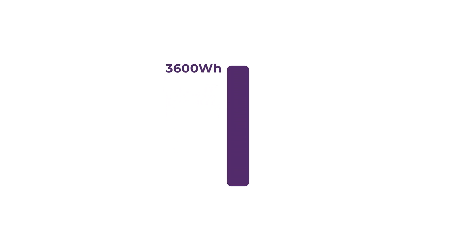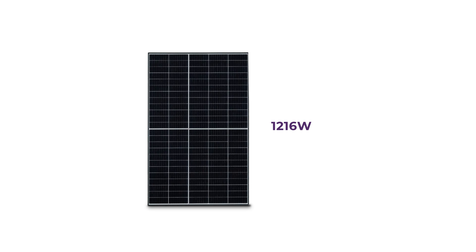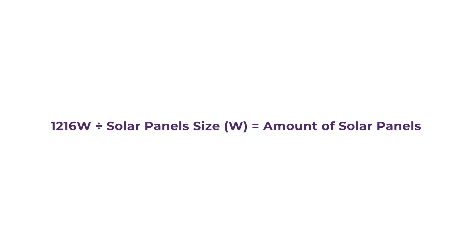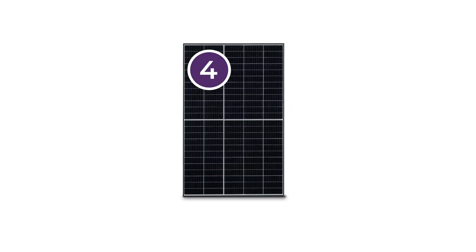For example, if you need to generate 3,600 watt hours a day to support your power use, you can then divide that by the peak sun hours. So 3,600 watt hours divided by 2.96 hours equals 1,216 watts. That means we need a solar panel array that is at least 1,216 watts. You then divide that by the size of your panels to know how many you need. Using 400 watt panels, the calculation is 1,216 divided by 400, which equals 3.04 — and because you can't have partial panels, we will need at least 4 solar panels.